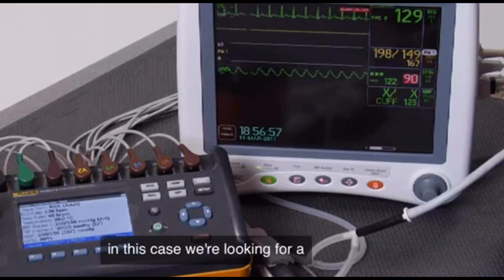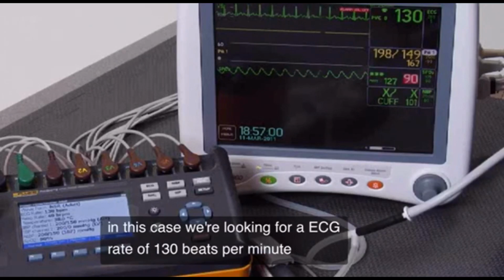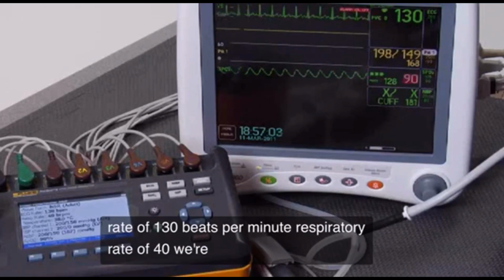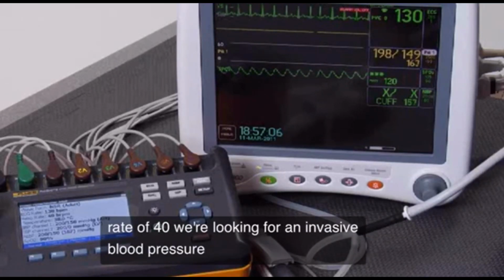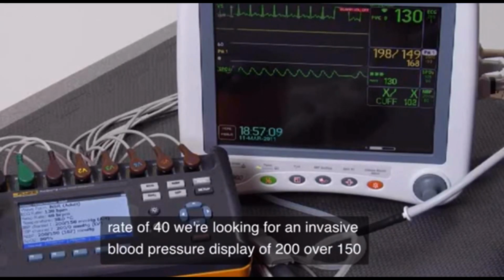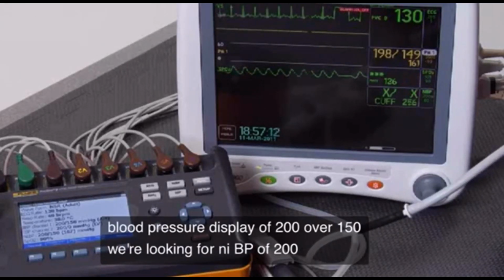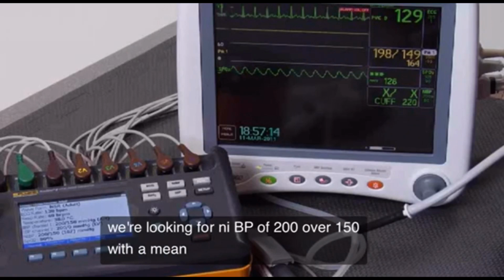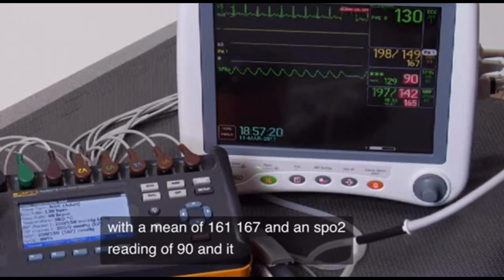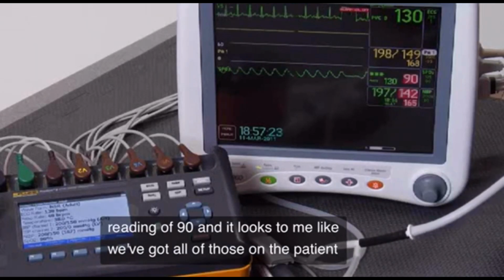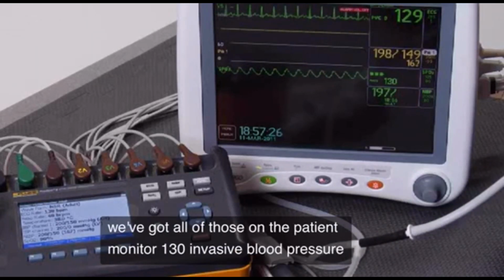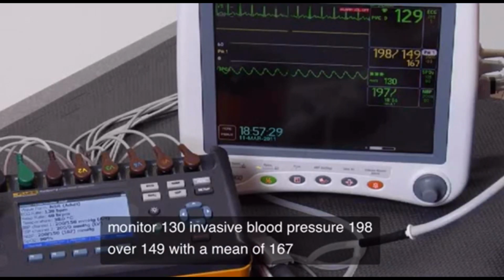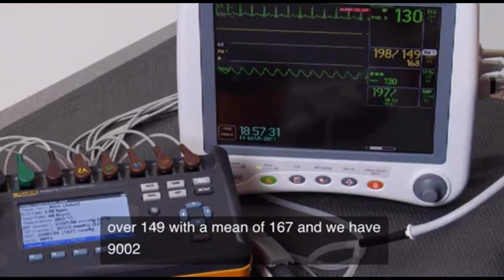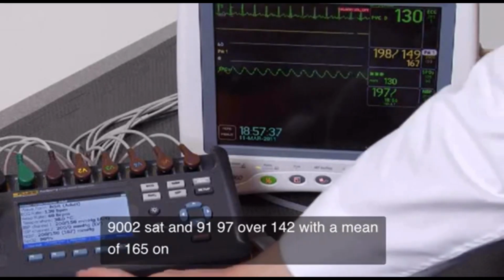In this case, we're looking for an ECG rate of 130 beats per minute, respiratory rate of 40. We're looking for an invasive blood pressure display of 200 over 150. We're looking for NIBP of 200 over 150 with a mean of 167, and an SpO2 reading of 90. And it looks to me like we've got all of those on the patient monitor. 130, invasive blood pressure 198 over 149 with a mean of 167, and we have 90 O2 sat and 197 over 142 with a mean of 165 on the cuff.